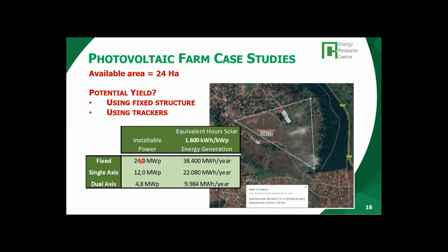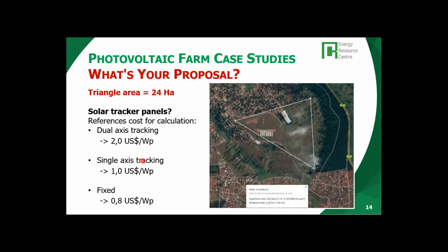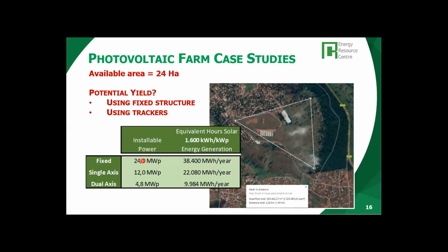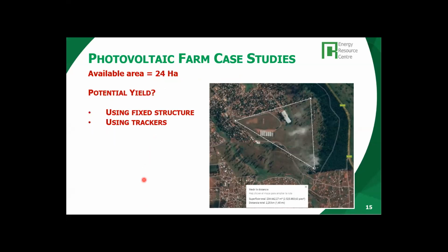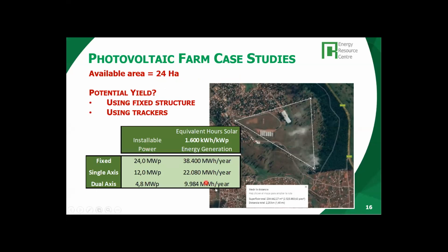The reference dollar per watt peak is the same as millions of dollars per million watt peak. It's probably easier to say it's the same for million dollars per megawatt or dollar per watt peak; it is the same relation. Exactly. So we multiply this by 0.8 because these cost references refer to the peak power capacity, the power of the plant, not the generation, not the energy.